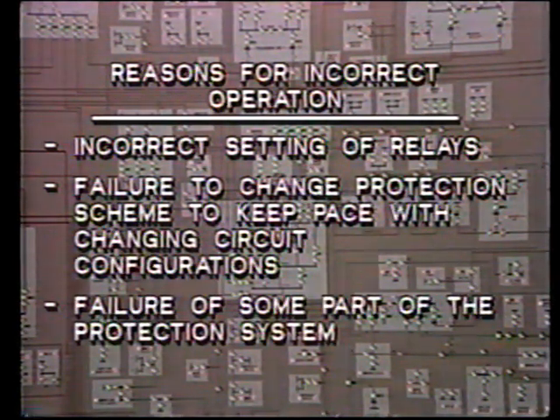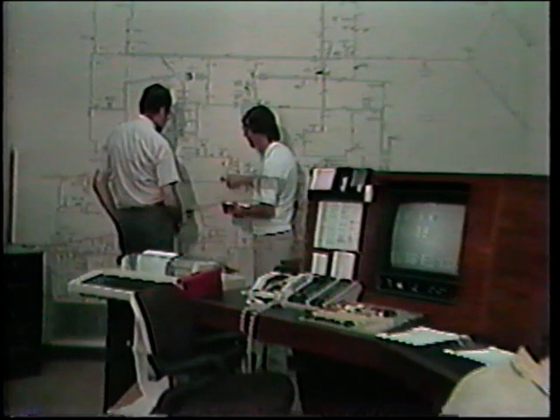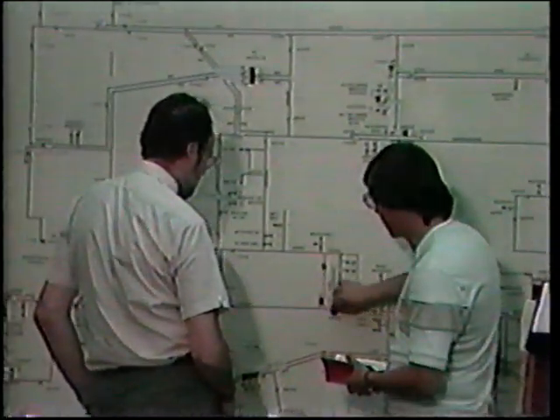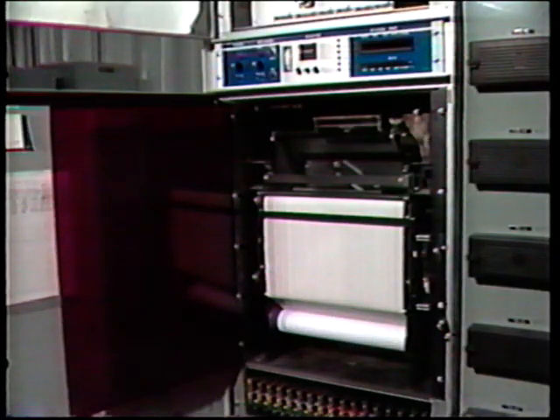The reason for incorrect operation of the protection system could be 1, incorrect setting of relays, 2, failure to change protection scheme to keep pace with changing circuit configurations, that is, inadequate protection, or 3, failure of some part of the protection system, such as the relays themselves, breakers, CTs or VTs, the station battery, the circuit wiring, and so on. With all of the variables involved, it's often quite difficult to carry out this post-mortem and deduce what actually happened. Fortunately for us, nowadays most power systems have installed data recording equipment, oscillographs and fault indicators that will indicate conditions before and after the fault. These provide valuable assistance in evaluating the actual performance of the protection system.